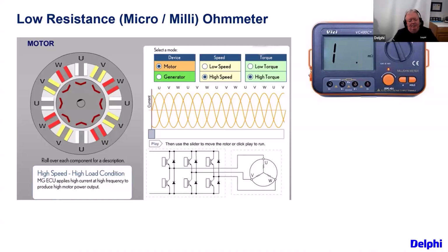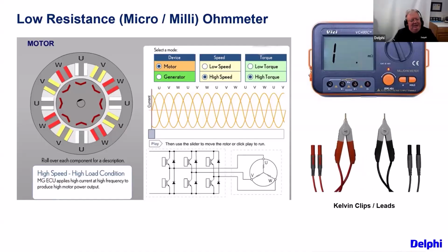You can use this meter, called a milliohm meter, which measures more accurately than a regular ohm meter. A regular ohm meter just goes between U and W and says that's 0.1 ohms. But you want to see, is it 0.1 or 0.08 or 0.07? That's what you really want to see - is there a big difference? The specs are in the newer manuals now for electric motors.